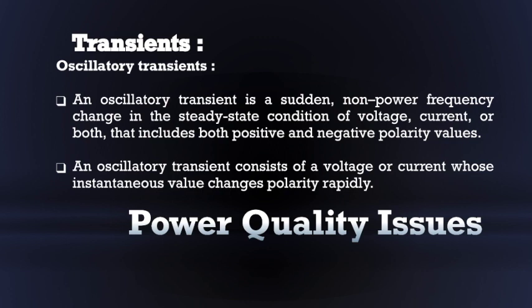Oscillatory transients again can be classified as high frequency, medium frequency and low frequency transients based on the frequency range and duration. Capacitive or inductive load switching is the most common cause of oscillatory transients. Switching on or off of the active power factor correction capacitors can also lead to oscillatory transients. They can also occur by abruptly turning off a motor load. In these situations, the system voltage will oscillate at a high frequency that decays within an electric cycle. The voltage overshoot occurs as a result of the oscillation and can affect equipment such as variable speed drives. In addition, the oscillation in the AC voltage can impact the voltage level of a drive's DC bus, potentially causing it to exceed its overvoltage trip point.